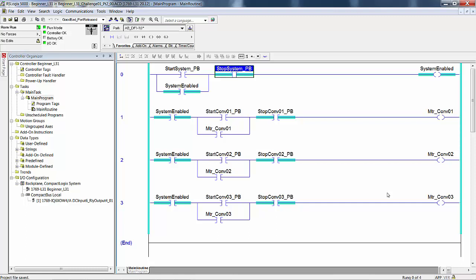We will add this logic after the rungs that you just created. We can do this only because we have not aliased our actual module-defined tag members with these tags that we have created. Otherwise, the state of the input members would override our simulation logic. So we're going to add logic that simulates releasing the push buttons. That way you don't have to toggle them on and toggle them off. You toggle them on and then they go off by themselves. You wouldn't be able to do that if these were aliased to input devices. You would have to operate the input devices because you cannot override the state of the input devices, in program mode or run mode.